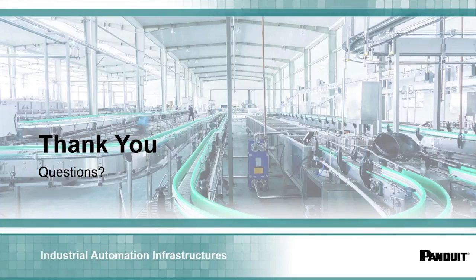Now with the switch connecting directly to the device, and then the PLC coming off of the device, and also the MES information being transmitted right through the switch, this no longer is required. So we can now have direct information, and the information can be shared with any device within the facility that needs it. You may have multiple devices who need the data from a device on the plant floor, and now they can share that seamlessly, and you don't have to do it programmatically.